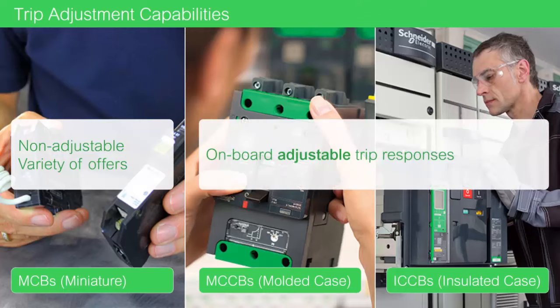Our molded case and insulated case circuit breakers do offer adjustable tripping by electronic means. In some molded case circuit breakers rated 250 amps and over, there is adjustment that can be made to the magnetic trip as well.